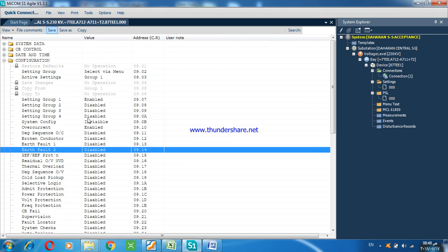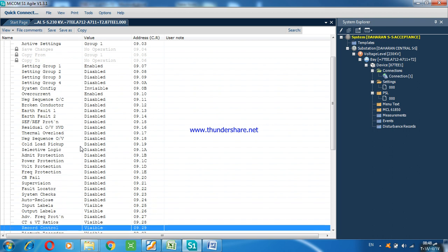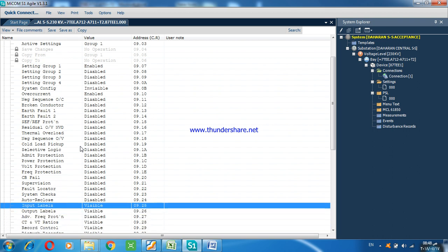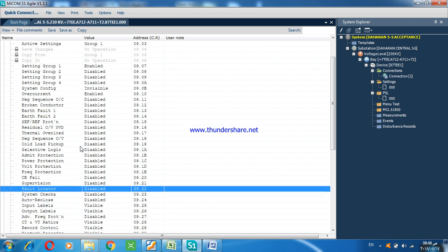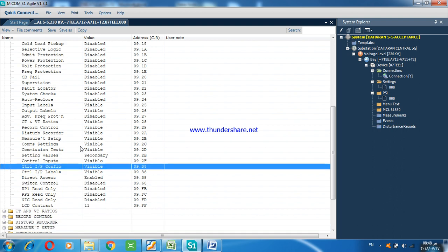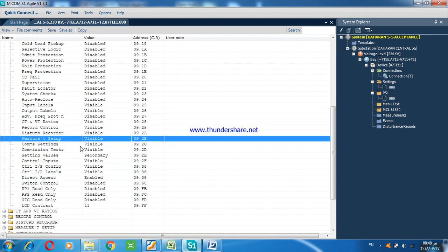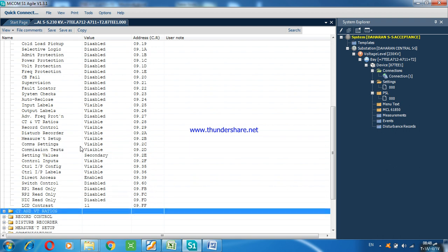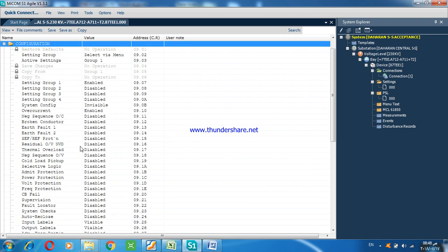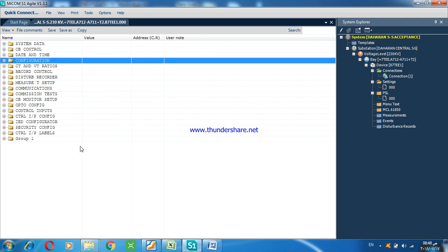Yes. Like that. After you make disable or enable, you have to save it as a file. Save, and once it changes, then you proceed for other. All other is disabled, like earth fault protection, frequency protection. We don't need them. These variables also come by default for input, output like this. So the setting file is nothing, just what parameters inside the relay we have to enable or disable, that is the function you want to do. Protections, yes.